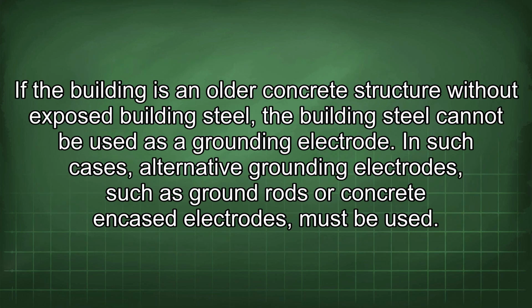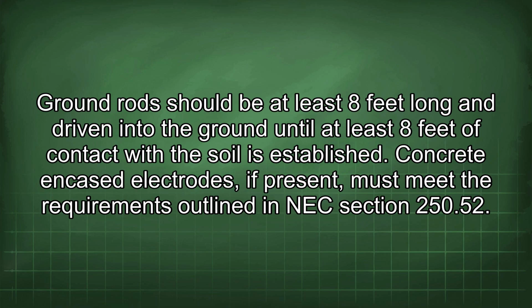If the building is an older concrete structure without exposed building steel, the building steel cannot be used as a grounding electrode. In such cases, alternative grounding electrodes, such as ground rods or concrete encased electrodes, must be used. Ground rods should be at least 8 feet long and driven into the ground until at least 8 feet of contact with the soil is established. Concrete encased electrodes, if present, must meet the requirements outlined in NEC section 250.52.